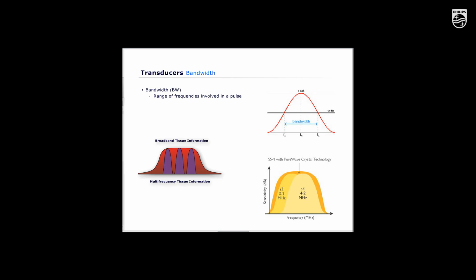Transducers resonate at a primary operating frequency, but the pulses produced contain a range of frequencies called the bandwidth. A narrow bandwidth means that the transducer can only operate effectively over a narrow range of frequencies. For example, a 5 MHz transducer with a narrow bandwidth may not work well below 4 or above 6 MHz.